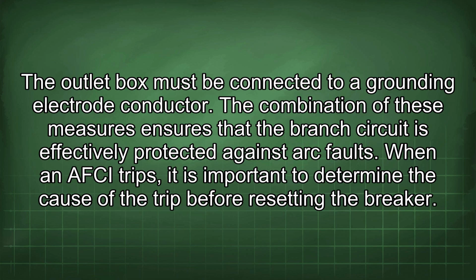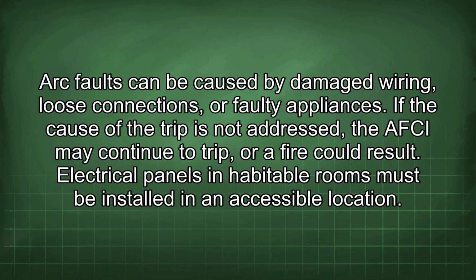When an AFCI trips, it is important to determine the cause of the trip before resetting the breaker. Arc faults can be caused by damaged wiring, loose connections, or faulty appliances. If the cause of the trip is not addressed, the AFCI may continue to trip or a fire could result.